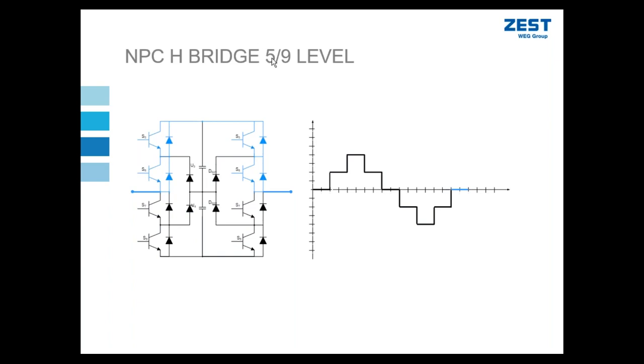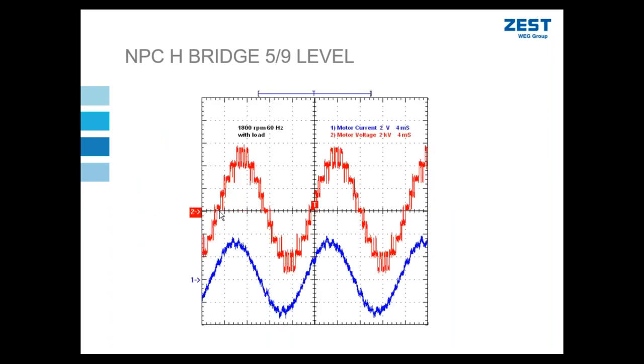We have five levels, so it's higher than the three levels that we get from a traditional NPC, neutral point clamp topology, which is three levels. This is five levels, but it's lower than what we would get from an H-cell multi-level inverter in 6.6 kV, which would be 13 levels. This shows an actual measurement of that voltage waveform phase to phase, as well as the current at the motor terminals.